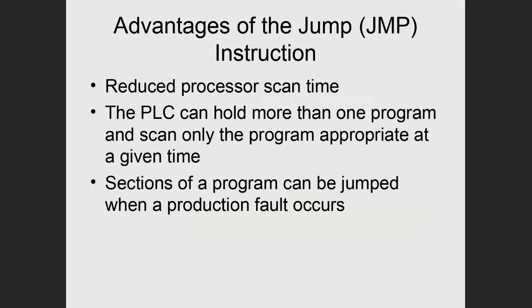This instruction does have some advantages. You can reduce the scan time, because if you jump over portions of the program, you don't have to scan the portions that you jump over. So one advantage is you can reduce scan time. Another advantage is you can have the PLC hold more than one program in one ladder, and you can jump to any program you want in a really long ladder. So you can use this to make your programming more modular, which is always nice, because it's nice to have structure in any kind of program.